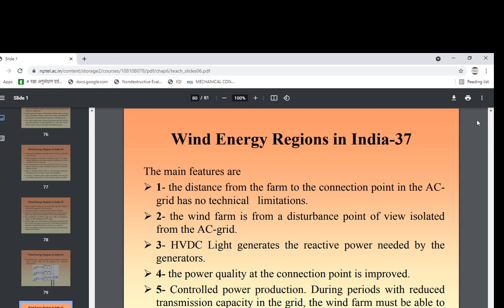The distance from the farm to the connection point in the AC grid has no technical limitations. The wind farm is, from a disturbance point of view, isolated from the AC grid. HVDC Light generates the reactive power needed by the generators. The power quality at the connection point is improved. Controlled power production is possible during periods with reduced transmission capacity in the grid. The wind farm must be able to operate at a reduced power level with all wind turbines running. No reinforcement in the AC grid is necessary.